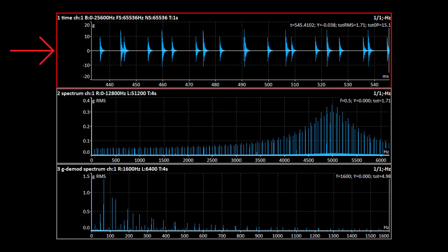The zoomed time signal clearly shows both sets of shocks. One for the outer race, the other for the inner race. The new set repeats with the inner race ball pass frequency, BPFI, which is 110 Hertz.